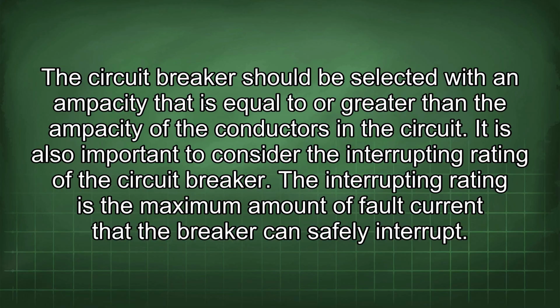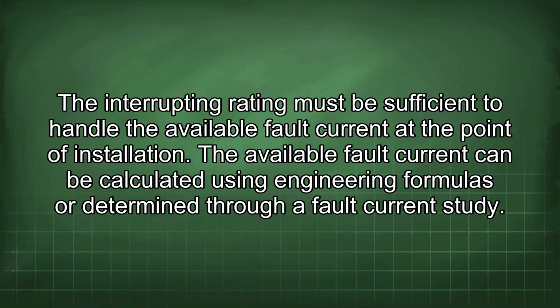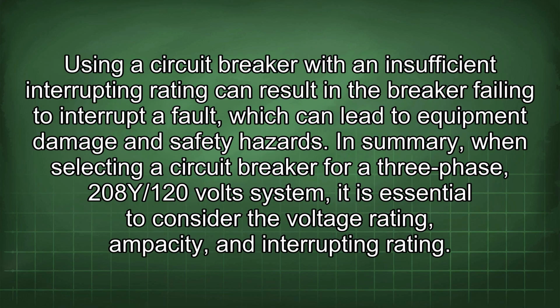The interrupting rating is the maximum amount of fault current that the breaker can safely interrupt. The interrupting rating must be sufficient to handle the available fault current at the point of installation. The available fault current can be calculated using engineering formulas or determined through a fault current study. Using a circuit breaker with an insufficient interrupting rating can result in the breaker failing to interrupt a fault, which can lead to equipment damage and safety hazards. In summary, when selecting a circuit breaker for a 3-phase 208Y/120V system, it is essential to consider the voltage rating, ampacity, and interrupting rating.